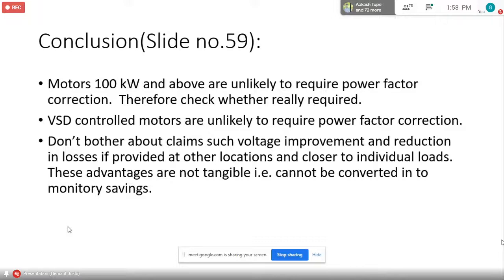So somebody tells you, okay, you provide it at the motor, and that way your cables have to carry less kVAR and less current, and you are saving in I square R, that is energy loss. You cannot calculate that tangibly. So don't worry. Provide it at the main switchboard, that's the most economic solution. All these things are good in the books, but not in the practical industry.